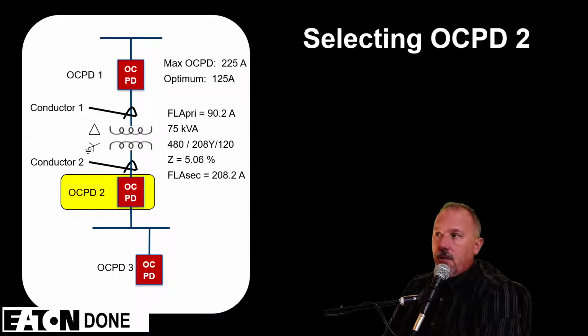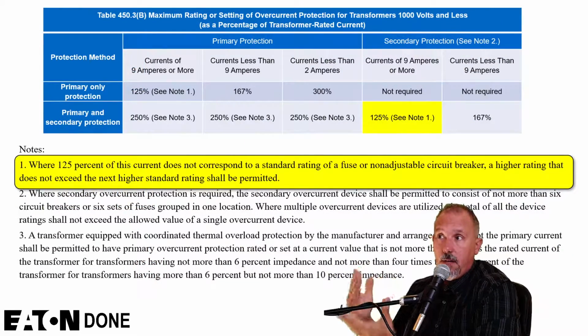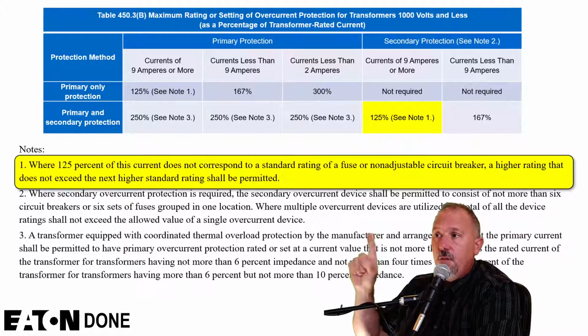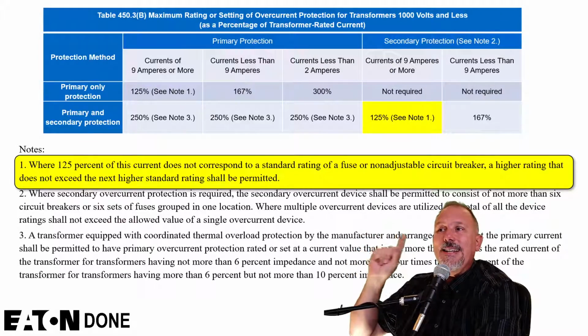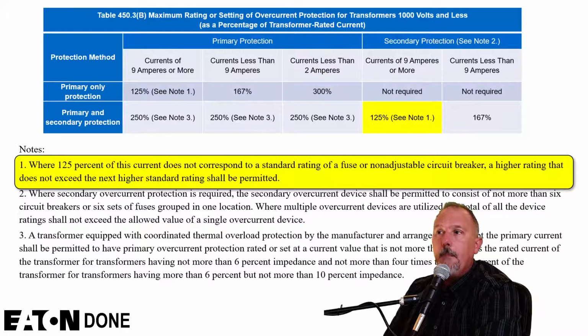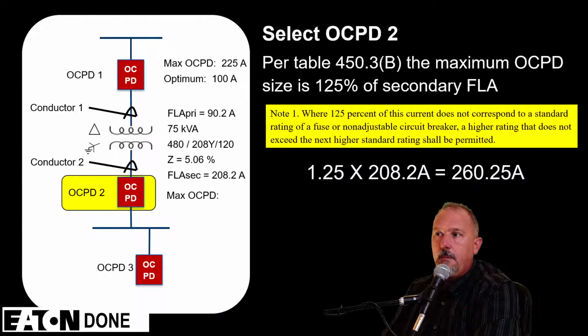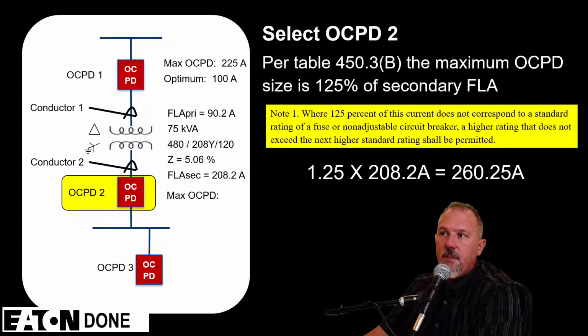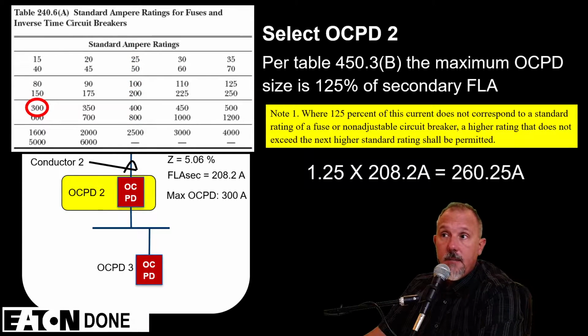And now, I'll just say that for the secondary overcurrent protective device, there is a maximum number that I can use based upon the National Electrical Code, and here it is. Secondary protection shouldn't exceed 125%. And note 1 says where 125% of this current does not correspond to a standard rating of a fuse or non-adjustable circuit breaker, a higher rating that does not exceed the next higher standard rating shall be permitted. So I can go to the next, and remember, the next standard rating is going to be based upon the table. So if I do the multiplications, 125% times 208 is 260 amps. If I look at my table 240.6(A), that tells me my next standard size higher than 260 is 300. So I could put a 300 amp panel board on the secondary of a 75 kVA transformer.